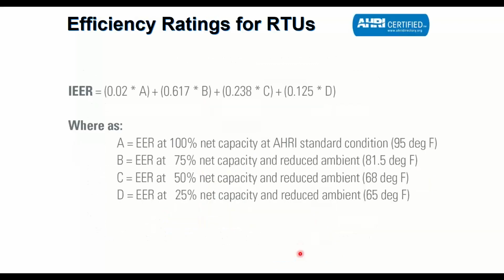But the way the IEER rating works for rooftop units and large split systems, they essentially rate the unit at 100, 75, 50, and 25% capacity, and then they weight those averages, with a big portion of it being on the B, which is 75% run capacity. So 61% of the weighting factor goes on this run point. 24% of the weighting factor goes on that. So pretty much all the weighting is going on the 50 and 75 point runs. Almost nothing, 2%, goes on the full load. And then down at the bottom, not very much either, because at that point, a lot of projects are already in economizer mode. So it's not that exciting to be efficient there. So basically running it at these points here.